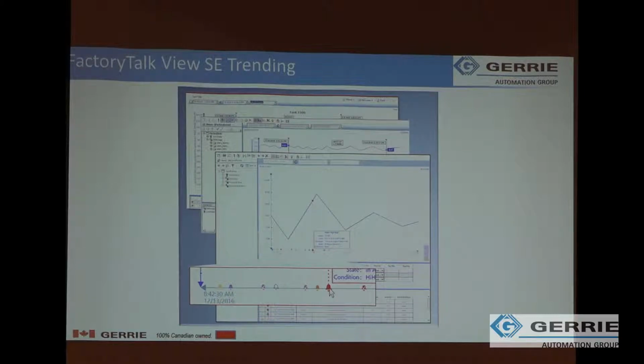We've got some reporting capability - you can see when alarms were triggered and where the variables were. This is a good example where it's not just trending a temperature or pressure or some other parameter in a plant, but we can actually trend and link the alarm data along with what we're trying to trend. It allows us, from an operations point of view, to do some analysis as to how they're related, or whether there's an unrelated alarm that might actually be related to the data. So this is the idea of analysis.